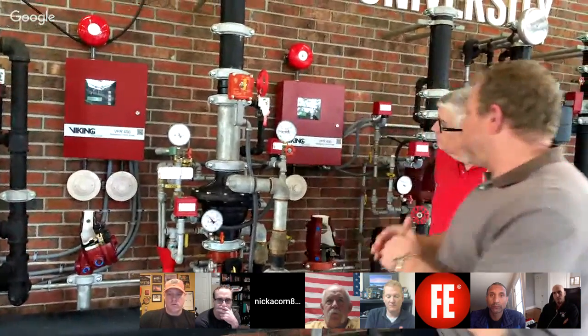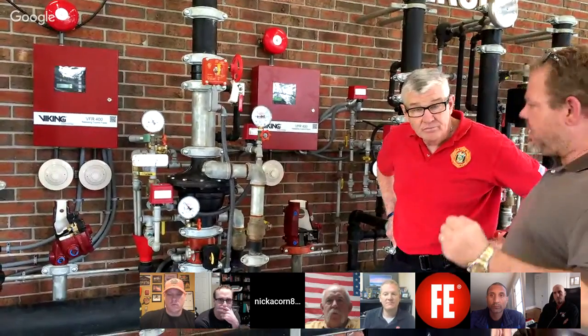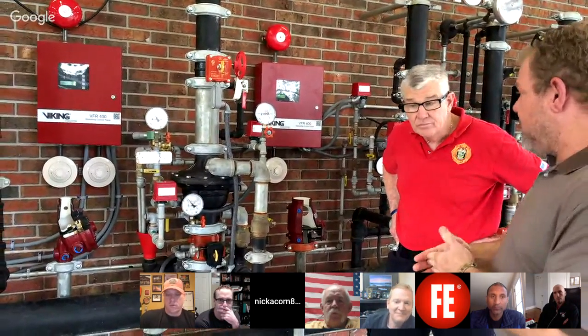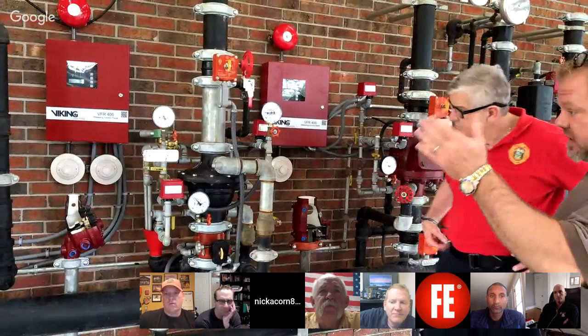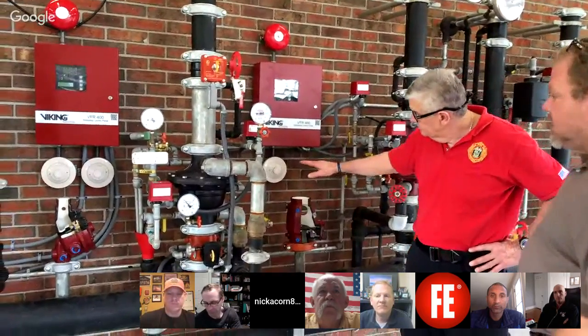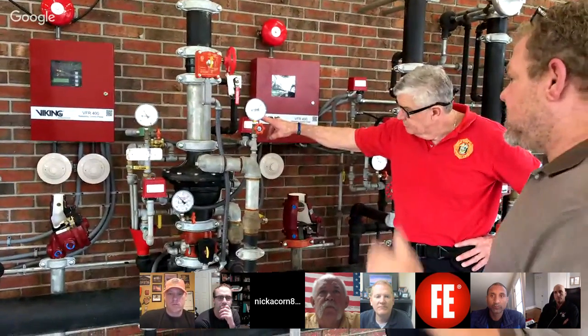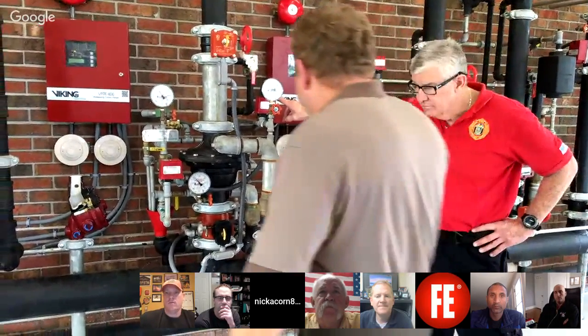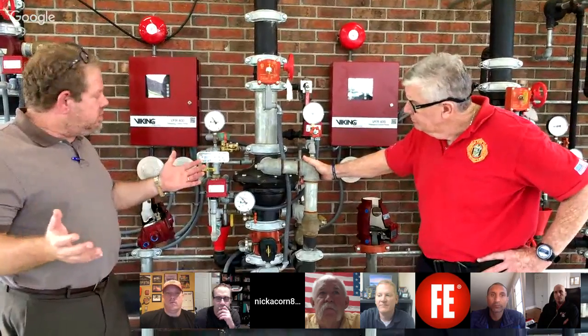What do we have here? It's a single interlocking preaction system, which we would normally see in a computer room. We would prefer the one to the left, which is a double interlocking preaction system. The difference is upon release of air, water enters the system, and air holds the water back to a certain location. Obviously, we all know that when a single head pops, air comes out of that particular sprinkler head, and then the water eventually gets to the head. We like the double interlocking a whole lot better because essentially it needs both forms of detection before the water fills. There's a little bit of a delay, but in that type of application, it's typically a secondary type of system. If you're putting this in a computer room, you're going to have a gas system. If the door were open, the gas were to deplete, and the fire would regenerate, the water sprinkler system would come into effect.